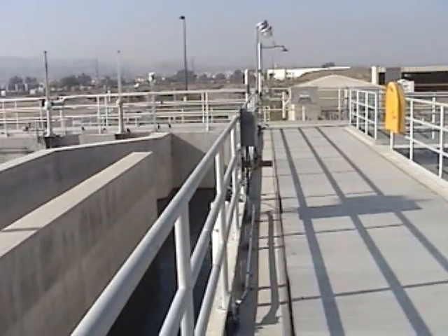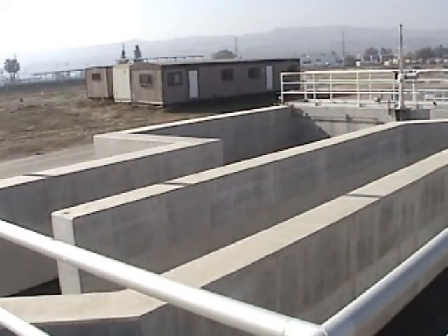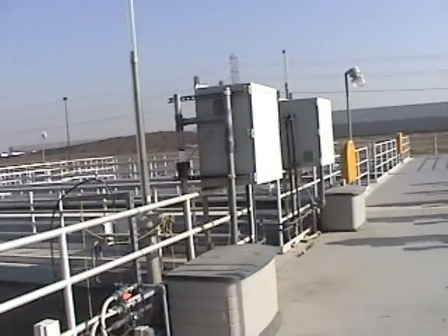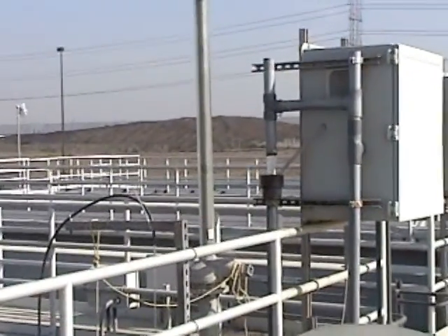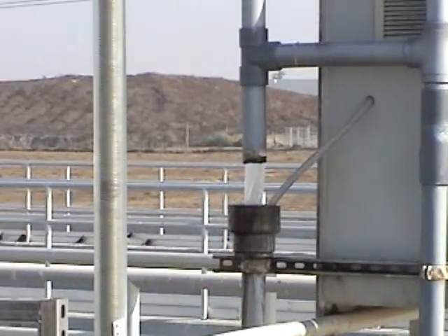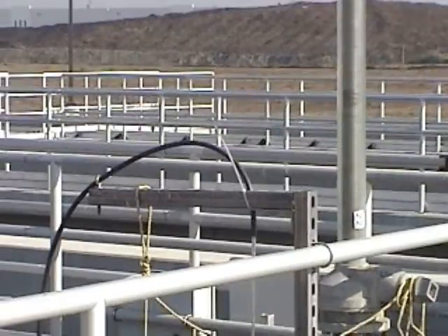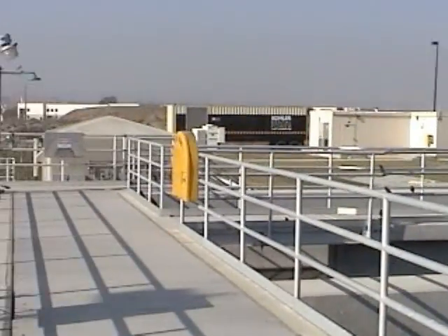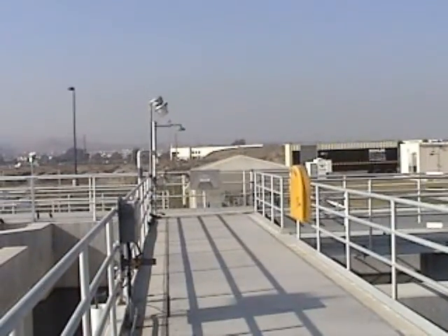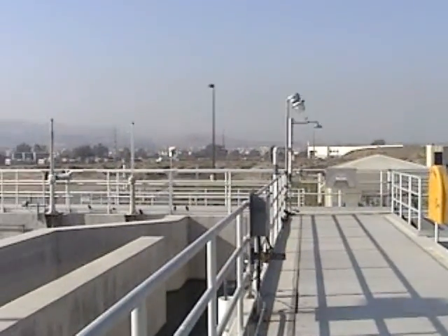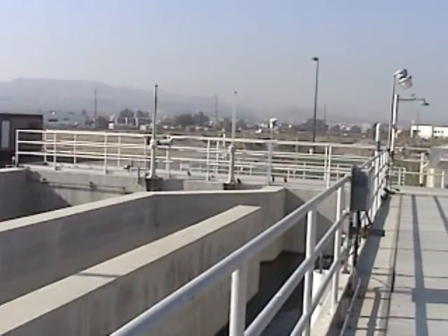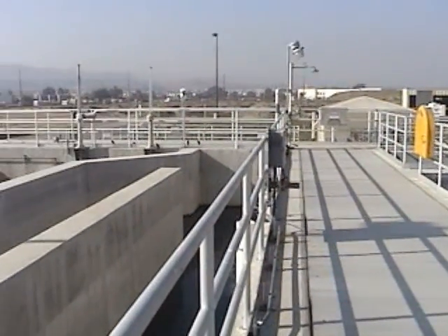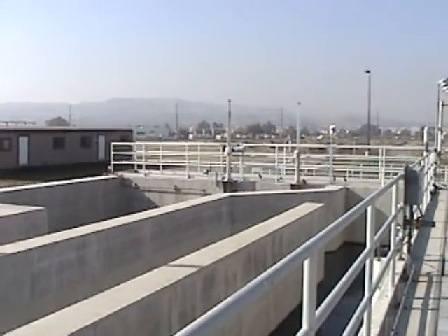So if you're on call at night, you can log in with a laptop and switch analyzers. If you switch analyzers though, and you do have a problem with it, let's say you switch over from the east to the west, and the west isn't working even though you've switched it on, the gate will still close because the Z-chlor will see it and signal that we've got chlorine out here, which is a discharge violation. It's going to shut the gate anyway. So there's a couple fail safes. During the night, you don't have to worry about going from an analyzer that was out of service to a malfunctioning analyzer. The Z-chlor will still catch that, and it'll still shut the gate.